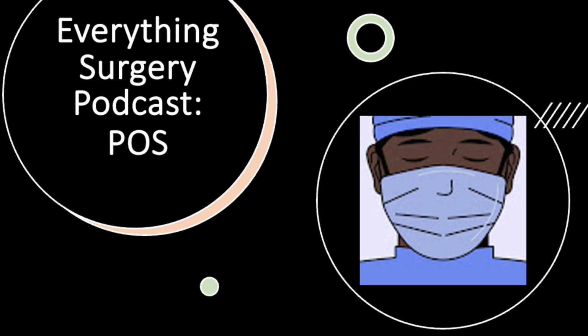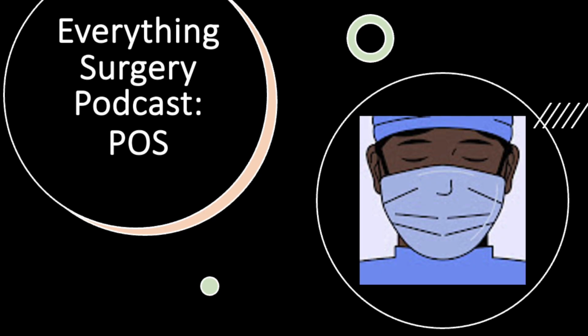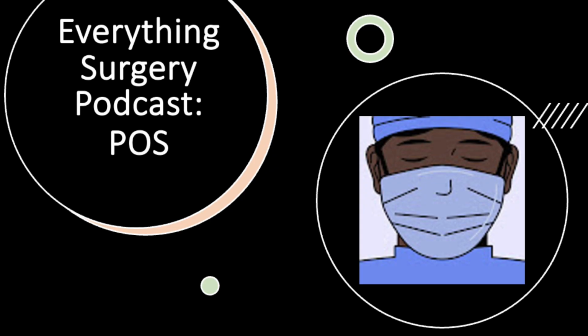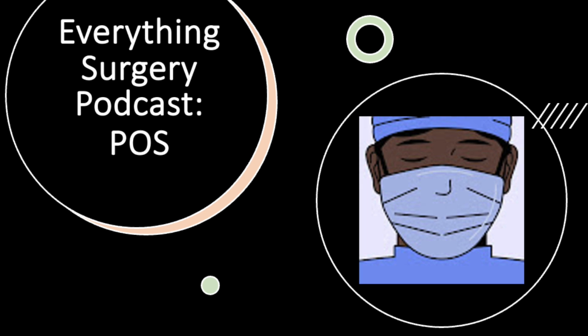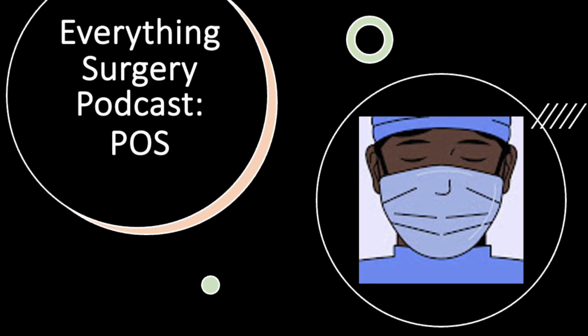After cleaning, each instrument is carefully inspected for damage, wear, and proper function. Think of checking the sharpness of scissors or the alignment of needle holders. Then, instruments are assembled into sets or trays according to the specific surgical procedure. Packaging is next, using materials that allow the sterilant to penetrate while keeping out contaminants until the instruments are needed. Common packaging solutions include peel-open pouches for individual items, textile wraps for trays, and rigid sterilization containers, reusable cases with special filters. Now, we move to the actual sterilization stage.